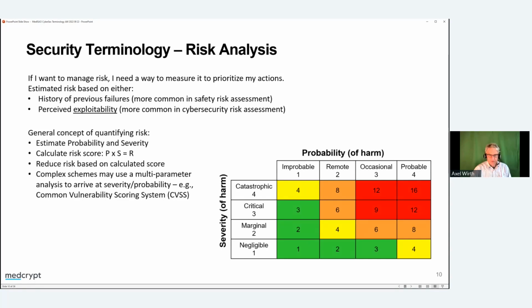A typical method for then estimating risk is that I estimate the severity of harm, meaning what would the impact be should this vulnerability be compromised, and the probability of harm, or how easy it would be to exploit a certain vulnerability or a certain software component. And then I can do a simple calculation based on, in this example, a 1 through 4 scale, multiplying those numbers, and I get then a risk priority matrix that helps me to determine where I should spend most of my efforts and most of my money on mitigating. Now, this is just an example of one way of estimating risk and probabilities. There are many other methods out there. There are other matrices out there that are being used.